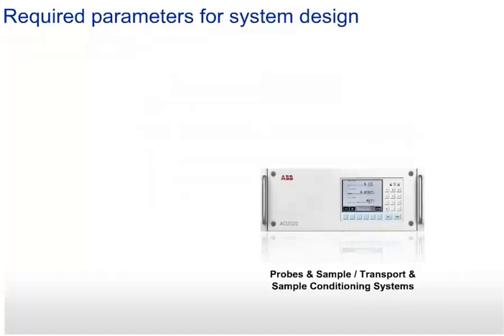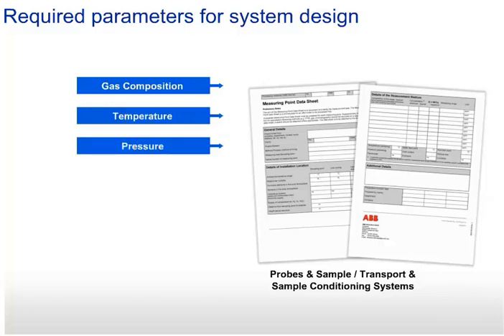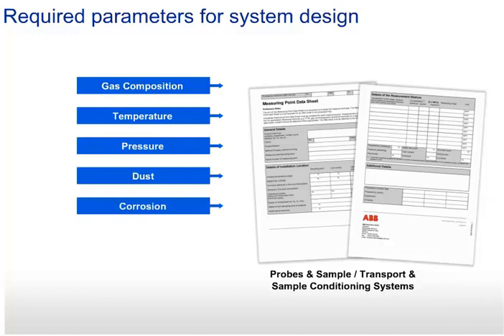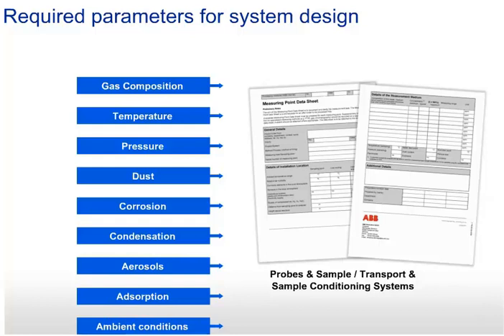Therefore, it is required to have exact information about the process gas composition and the ambient process parameters. A special form called a measuring point data sheet guides customers while filling in all the relevant aspects of their measurement task, like: the gas composition including the measuring component and all participating gases; temperatures of the process gas; dust load and particle size; components in the mixture that can cause corrosion or lead to corrosive condensation and aerosols inside the analyzer sensors; gases that can be adsorbed by solid surfaces; and more information about ambient conditions like the classification of hazardous areas.